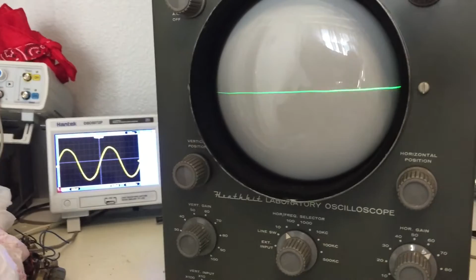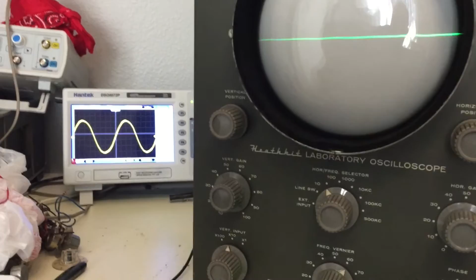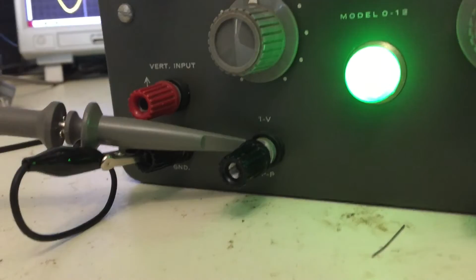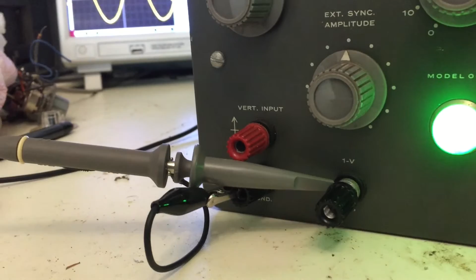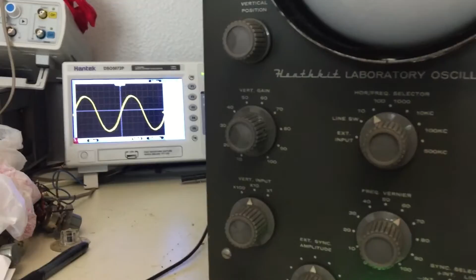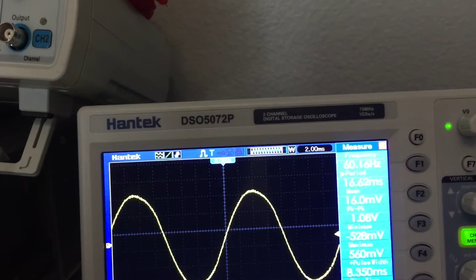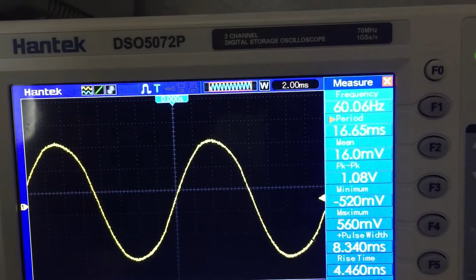As almost a twisted bit of irony, since we're still measuring voltages, I would be remiss if I did not measure the 1 volt AC sinusoidal peak-to-peak voltage coming off the test point of this unit. This is supposed to be a calibrated AC that's used for this oscilloscope. So having only one other working oscilloscope on hand, I've connected it to this oscilloscope. And indeed, we see a value of 60 hertz, which is obviously expected, 1.08 peak to peak, which is pretty good for this unit. Quite impressed. I shouldn't be too impressed though, because I think it's just right off the coil. And I think if we kicked up the voltage over here, we would see that go up.